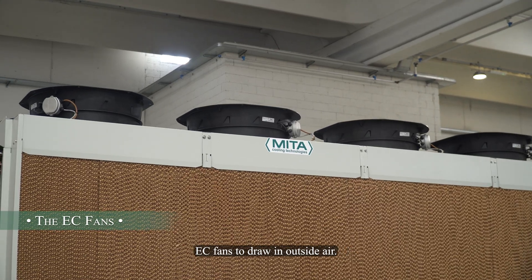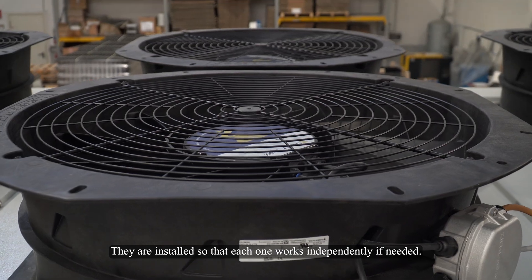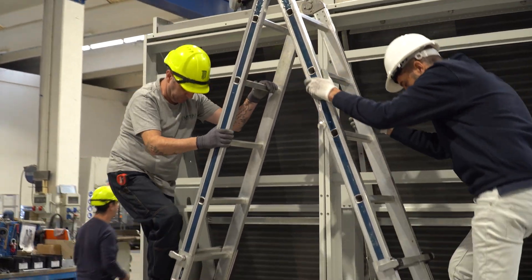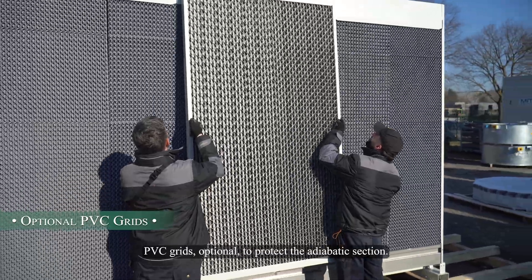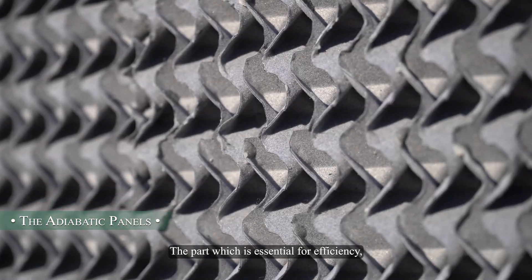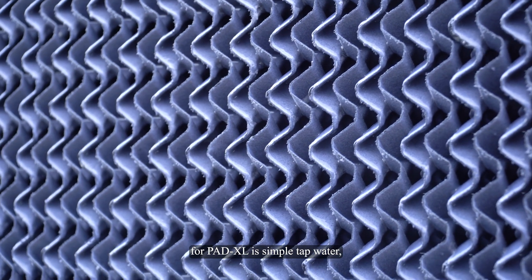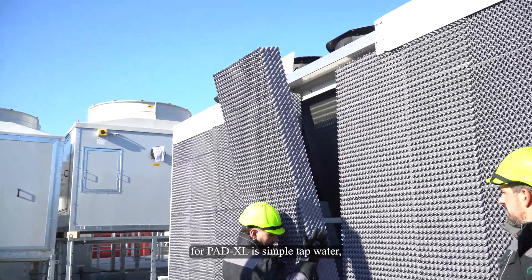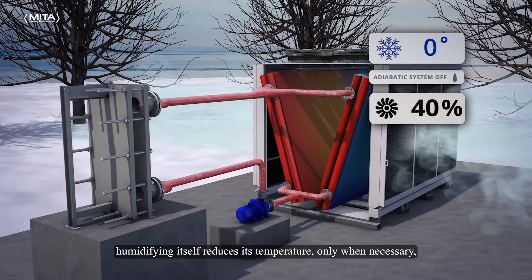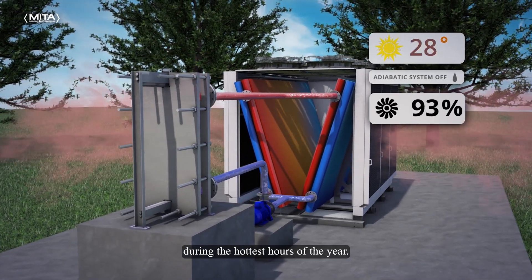EC fans draw in outside air; they are installed so that each one works independently if needed. PVC grids are optional to protect the adiabatic section — that part which is essential for efficiency — a surface which is humidified with simple tap water, so that the air, the cooling element, by humidifying itself, reduces its temperature only when necessary during the hottest hours of the year.